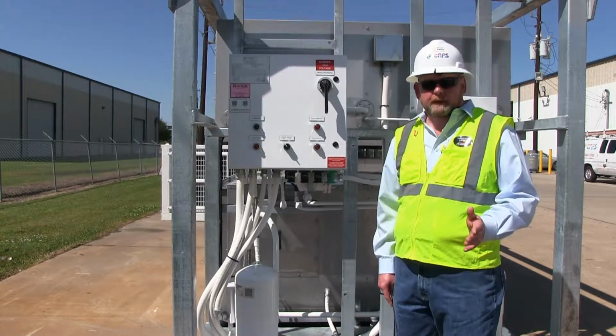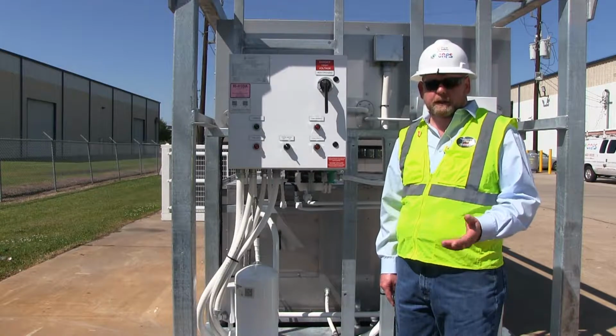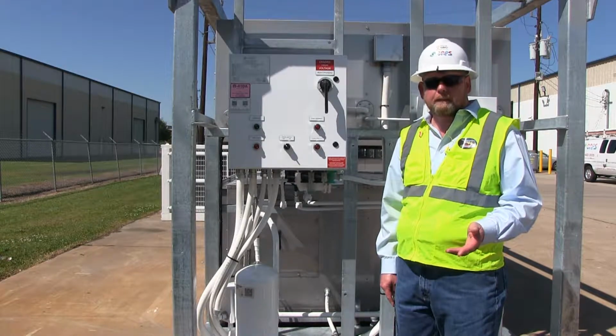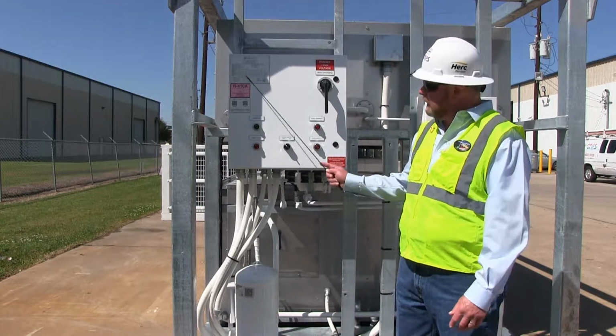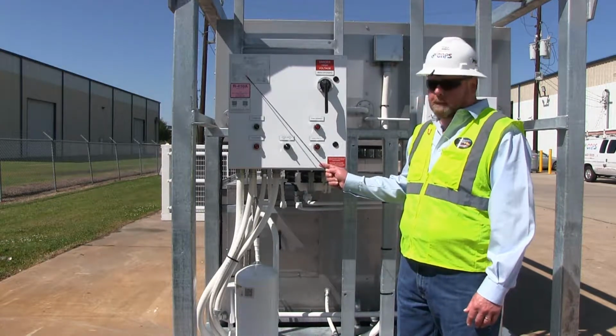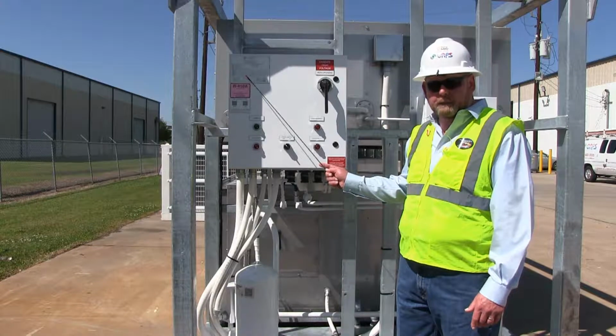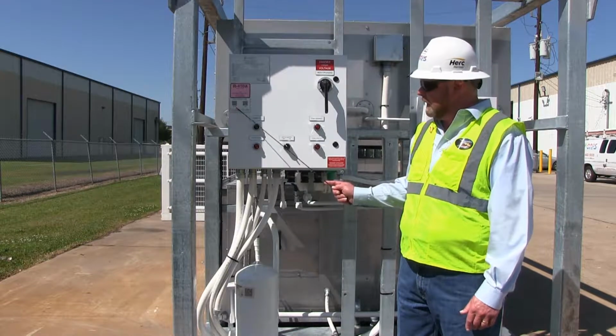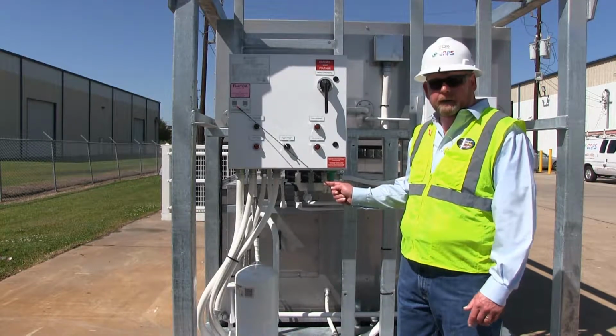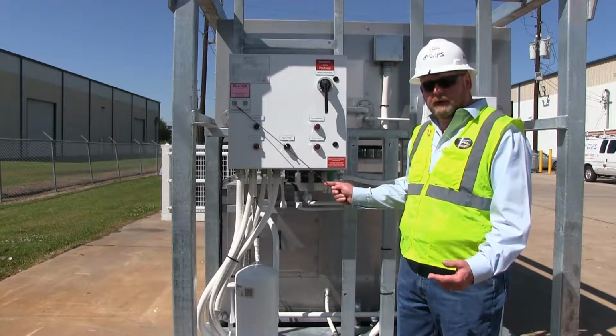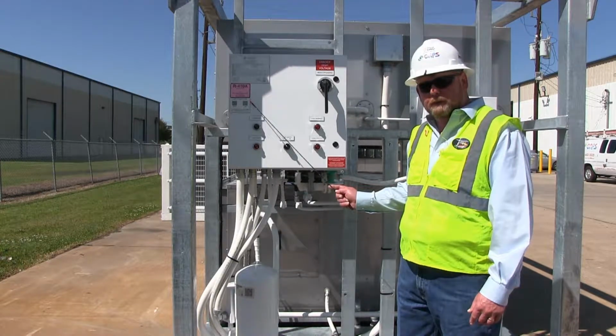After the unit's been placed in a permanent position for the installation of the particular job, you'll need to look at the data tag on the unit to ensure that the proper power requirements are provided to the machine. Additionally, if you have any questions, there's a QR tag here that can be scanned to watch video or reference the IO&M manuals.